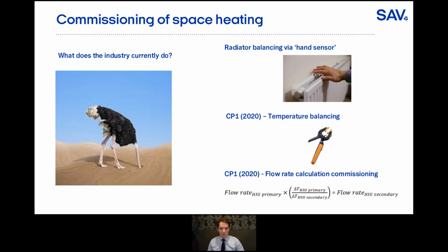The three modes, the three ways that I see out in the industry of how we can commission. The first one, and hopefully we'll never see this ever again, is radiator balancing via the hand sensor. Making sure you've got heat at that radiator is not a good way of understanding whether your radiators are balanced properly and ensuring you've got that low return temperature.